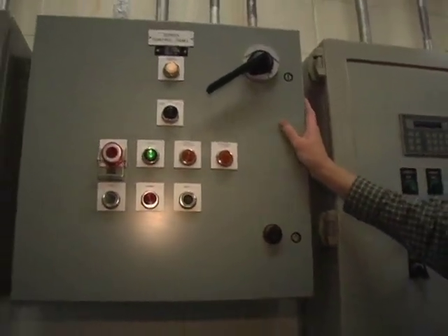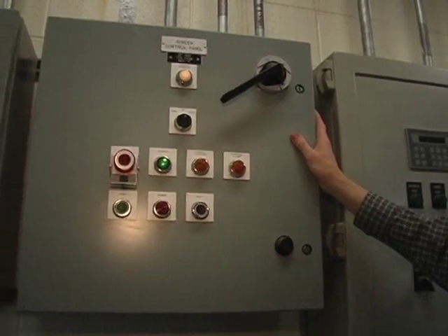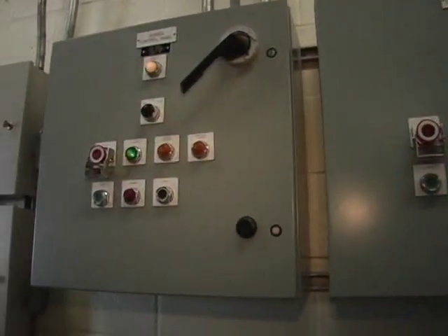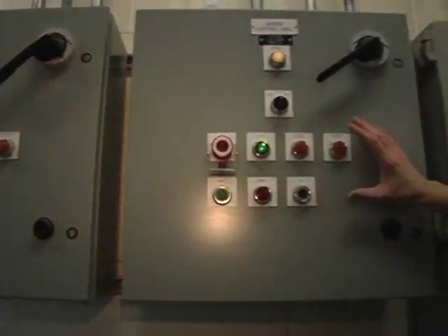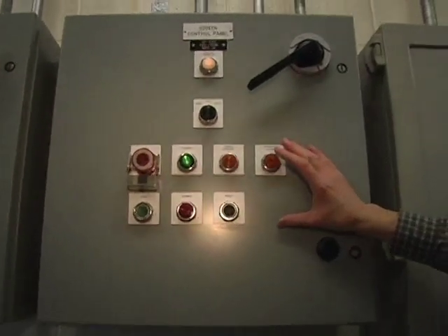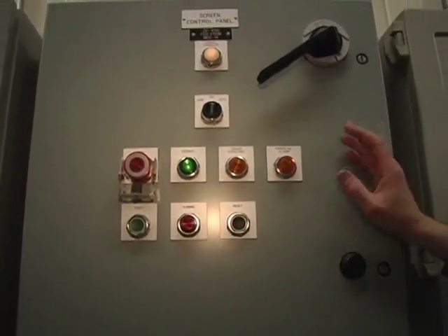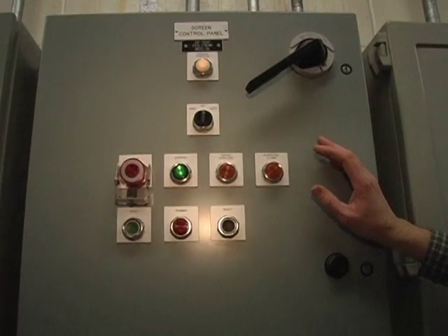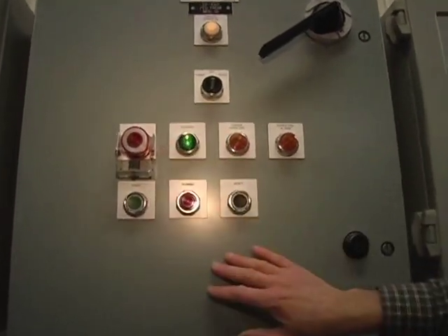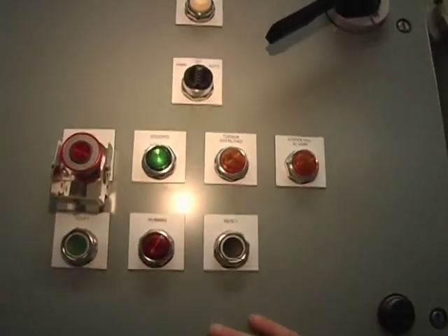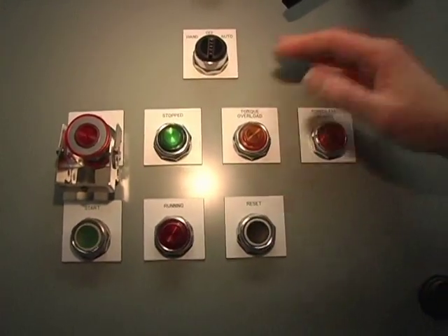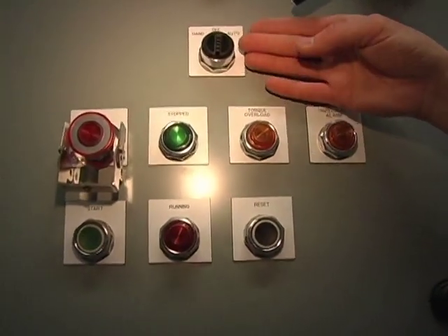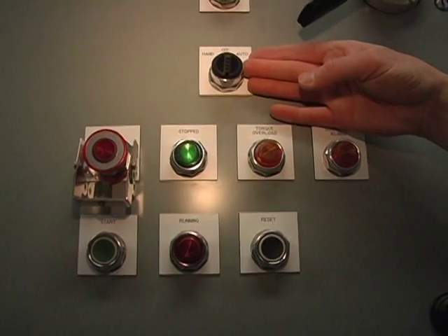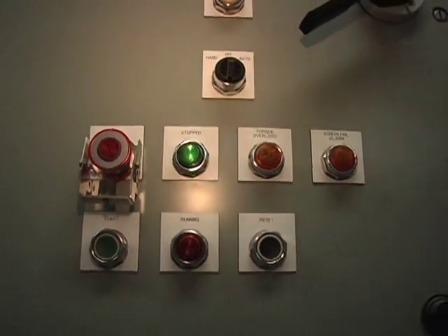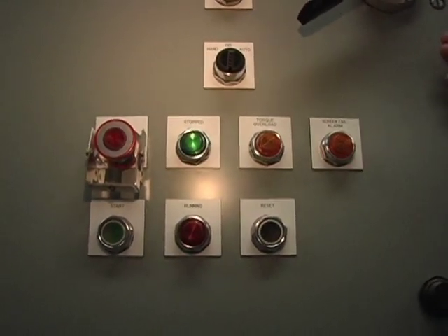Beyond that panel is the bar screen control panel. There's one for each bar screen. You have local control of the equipment from this location. If your hand switch in the field is set to the automatic mode, then you can start and stop the equipment from this location. If that is set in the automatic mode and the hand switch here is set to auto, then that transfers control to the SCADA system.